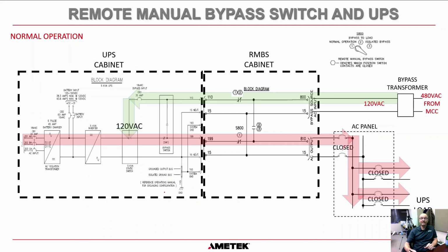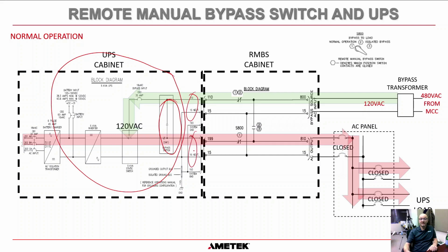And to be able to do that, you can install an RMBS cabinet, or a remote maintenance bypass switch. Okay, now let me explain this drawing. This drawing is exactly the same drawing that we had before. We have this UPS here, and it has this internal maintenance bypass switch here. And remember, if we used that, these terminals here would still be hot, even if we go to maintenance bypass and isolate the battery and the AC input. But with the addition of an external RMBS, we can in fact make that system volt free, and we'll show you how.